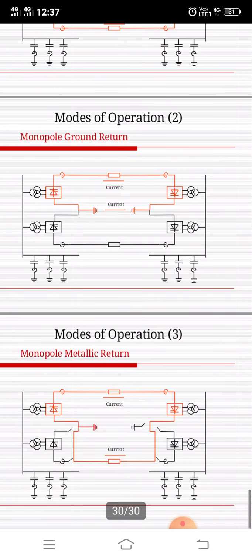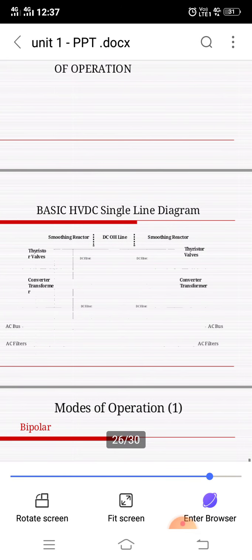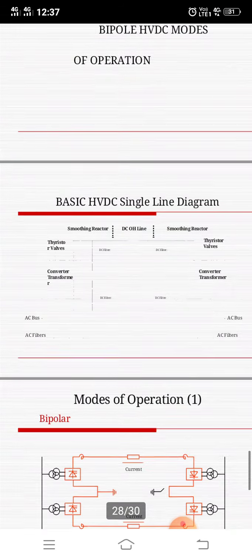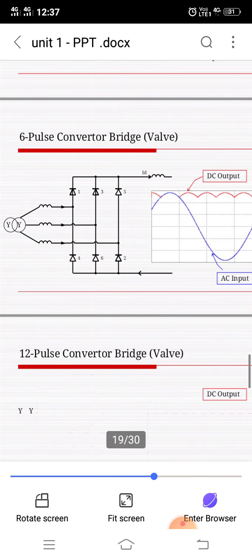In a 12-pulse group and converter transformer configuration, HVDC converters are usually built as 12-pulse circuits. This is a serial connection of two fully controlled six-pulse converter bridges and requires two three-phase systems spaced apart by 30 electrical degrees. The phase difference serves to cancel out the six-pulse harmonics on the AC and DC sides. This combination is commonly used in HVDC converter stations.